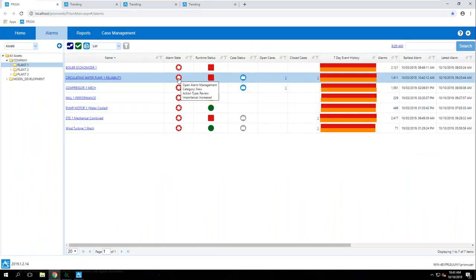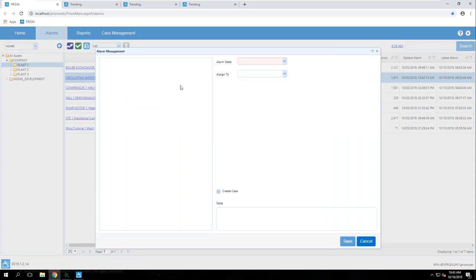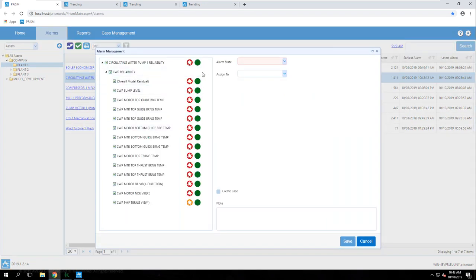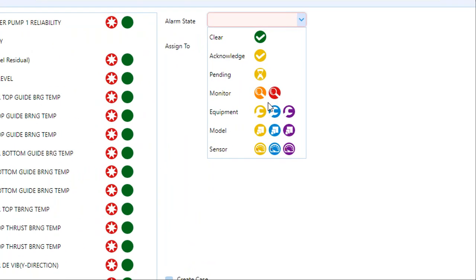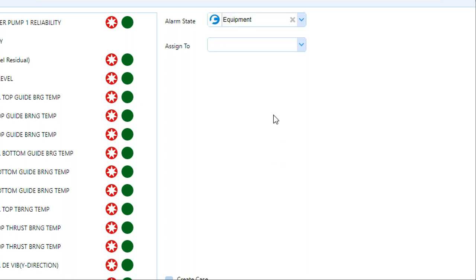Now, just coming back over again, if I was a user monitoring this system, I would jump into our built-in workflow tool. You can see here all of the alerts and warnings generated for this piece of equipment, and I would set it to some kind of state, whether this is a new alarm that we want to acknowledge and watch further. We'll monitor this piece of equipment over time to see how it's degrading or if it's getting better. If we know it's an equipment or model tuning issue, or an instrumentation issue, we can assign all of that in the workflow here.